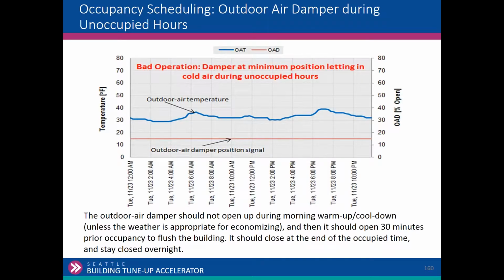Here's another: outside air damper open during unoccupied hours. So here's the outdoor air temperature. Here's the outside air damper position. It doesn't go below 15%. So it's not closing at night. And if the outside air damper is open and not closing, might as well leave the window open. That's a pathway from your return air through the unit to the outside. So that's a window left open.